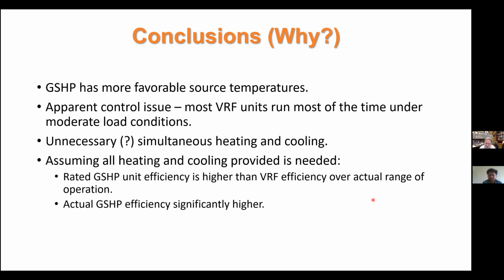analysis. And this apparent control issue also shows up as apparently unnecessary simultaneous heating and cooling. And then if we assume, as we did in the COP and EER analysis, that all the heating and cooling that is provided is needed, we've got higher ground source heat pump unit rated efficiencies, and then the actual efficiency of the heat pumps is significantly higher. So all those things add up to improve performance for the ground source heat pump system.